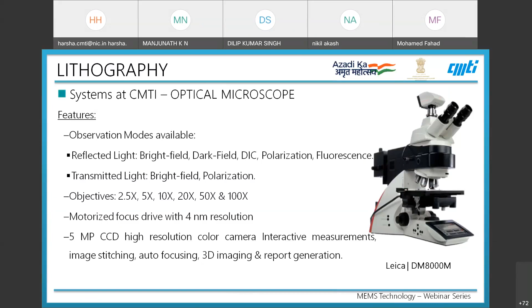And the optical microscope from Leica, which we use for optical inspection, is capable of bright field, dark field, DIC, polarization, and fluorescence options under reflected light, and under transmitted light, it has bright field and polarization. It has a maximum objective of 100x and a motorized focus drive with 4 nanometer resolution. Image stitching, autofocusing, 3D imaging, report generation, and interactive measurements are special features of this particular microscope.